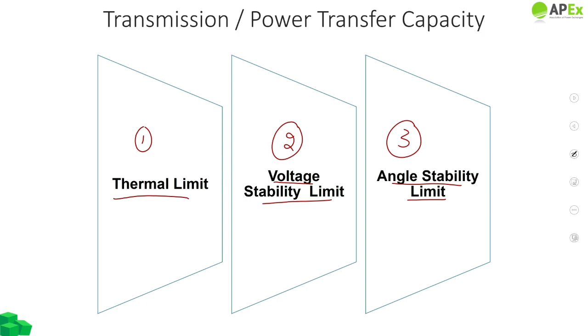So now let's discuss thermal capacity limits in detail. We know that when the power flow in a line increases, the current passing through the line also increases, right? And the increasing current produces more heat. From fundamental physics, we have learned that when a material or a conductor is heated, it expands. And since the conductor is suspended between two towers or two poles, this expansion would cause it to sag further. Over time, once the conductor is heated beyond its recommended material limits, this expansion makes it lose its strength. There could be instances when a conductor is overheated and it collapses or falls down.